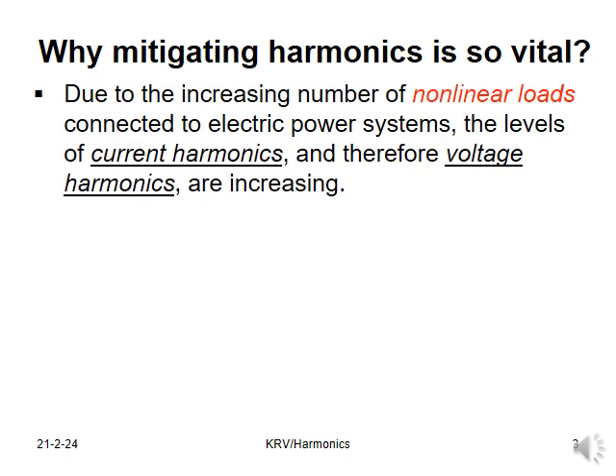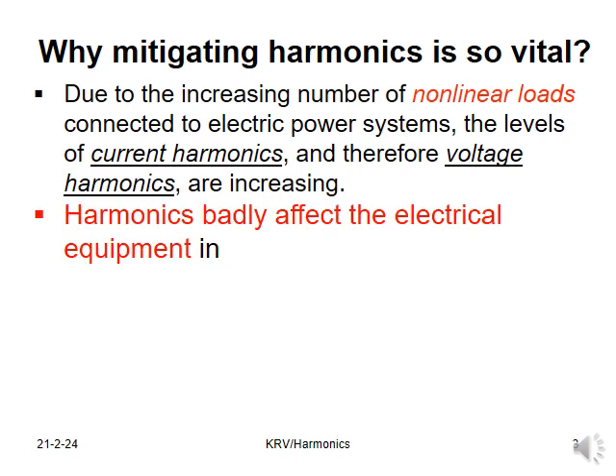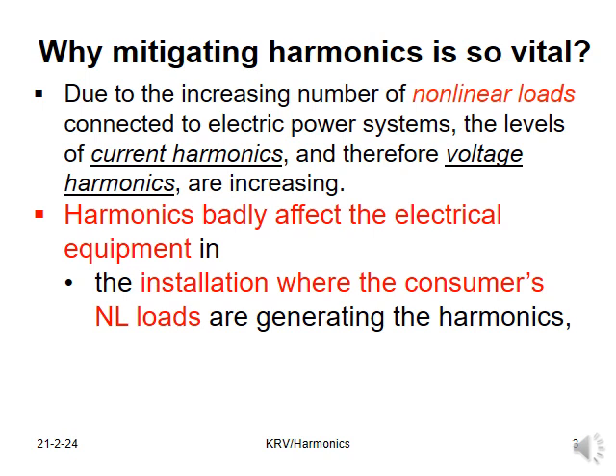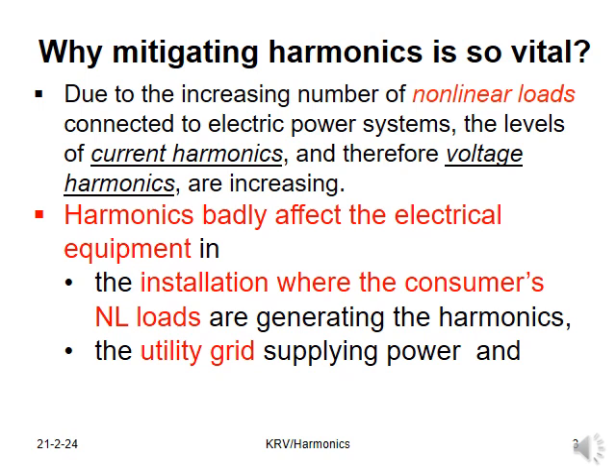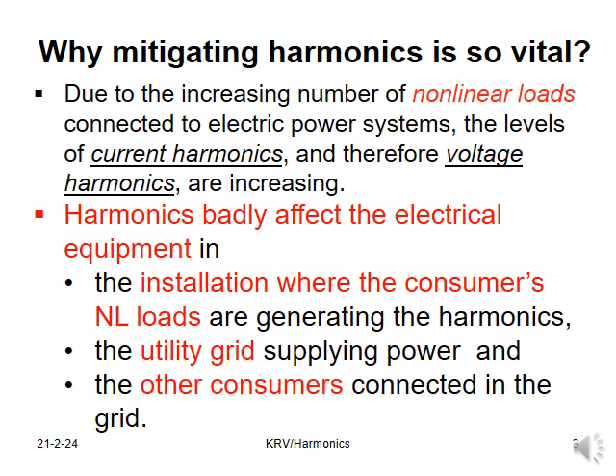Why is mitigating harmonics so vital in the present scenario? Due to the increasing number of nonlinear loads connected to electric power systems, the levels of current harmonics and therefore voltage harmonics are increasing. Harmonics badly affect the electrical equipment in the installation where the consumer's nonlinear loads are generating the harmonics, the utility grid supplying power to the consumers, and the other consumers connected in the grid.